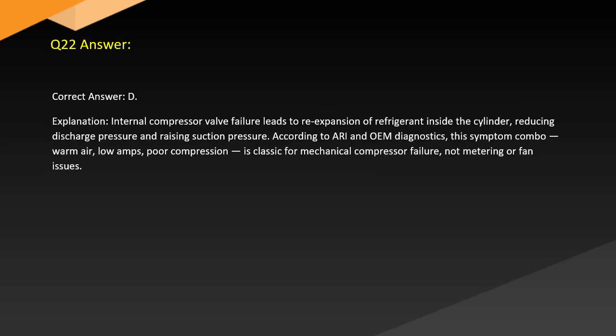Answer. Correct answer: D. Explanation. Internal compressor valve failure leads to re-expansion of refrigerant inside the cylinder, reducing discharge pressure and raising suction pressure, according to RSES diagnostics. This symptom combo, warm air, low amps, poor compression, is classic for mechanical compressor failure, not metering or fan issues.